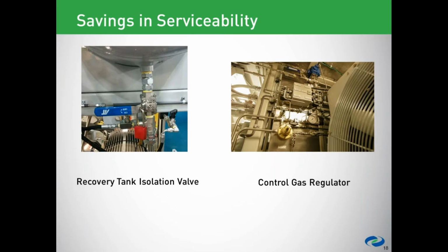And then the final item, the control gas regulator. So we use a high-pressure gas regulator to reduce the discharge gas down to 100 psi, which can then be used for actuating pneumatic valves. And this also eliminates the need for an air compressor on site to use pressurized air for this.